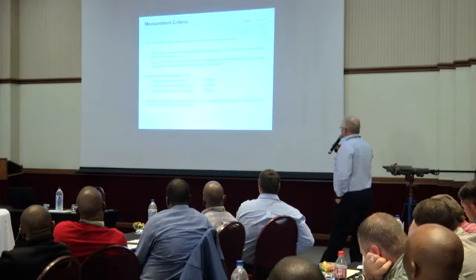And that is from the original. If you look at the guideline for the compilation of the Code of Practice, Annexure 2, as well as the guidelines that have been sent out by the DMR in 2006, it requires the Type 2 integrating instrument. The measurement criteria according to SANS is: the criterion level must be 85 decibels, the threshold limit is 80, and the energy exchange rate, or the doubling, is 3 decibels. Although the instrument supplier normally sets these measurement criteria prior to delivery, the user must confirm the criteria.